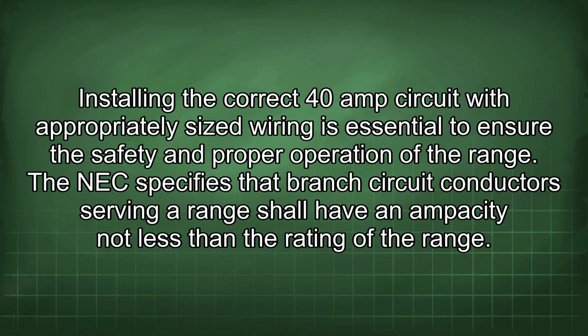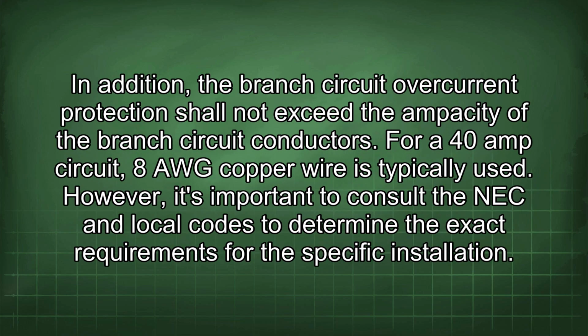The NEC specifies that branch circuit conductors serving a range shall have an ampacity not less than the rating of the range. In addition, the branch circuit overcurrent protection shall not exceed the ampacity of the branch circuit conductors. For a 40 amp circuit, 8 AWG copper wire is typically used. However, it's important to consult the NEC and local codes to determine the exact requirements for the specific installation.